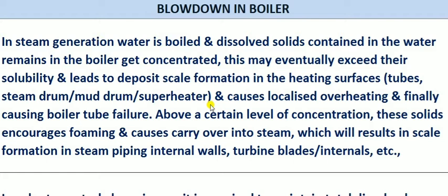After certain conditions, if we do not maintain the level of concentration, there is a possibility of solid carryover to the steam, which will cause scale deposition in the pipelines. It can even carry over to the turbines and turbine blades as well, which would reduce the turbine efficiency. So blowdown plays an important role.